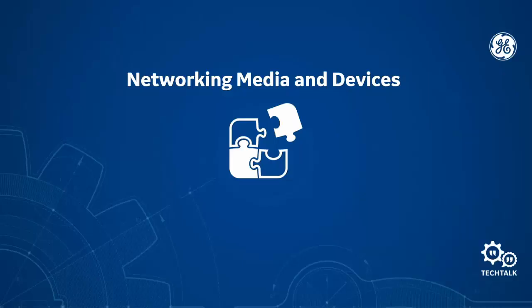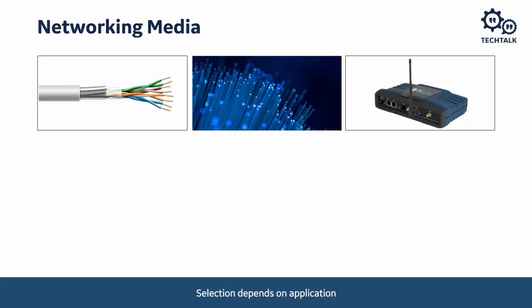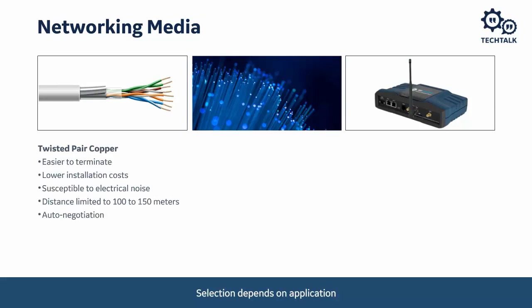Let's get familiar with the media types and devices typically found in a substation network. There are three basic types of networking media. Most of us are familiar with the twisted pair copper, commonly used RJ45 cable — there are different categories of these cables. The advantage is they are easy to terminate, being copper connections at lower installation cost. The disadvantage is they can be susceptible to electrical noise and are limited in distance, but they can auto-negotiate the speed, supporting 10 megabits, 100 megabits, and 1 gigabit interfaces.